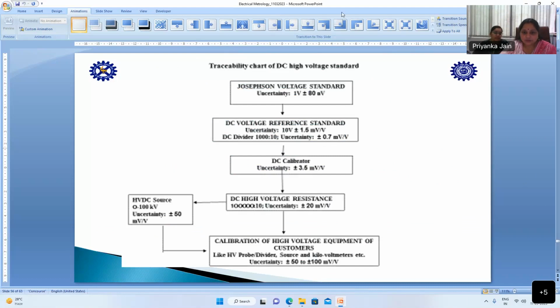So we have a high voltage Josephson voltage standard. The uncertainty is 80 nanovolts, and from this we have a DC voltage reference standard with an uncertainty of 1.6 millivolts, and a DC divider ratio with an uncertainty of 0.7 millivolt. And we have a DC calibrator, its uncertainty is 3.5 microvolt per volt, and a high voltage resistance divider of 10,000 to 1 ratio. The uncertainty of the high voltage resistance divider is 20 microvolt per volt.